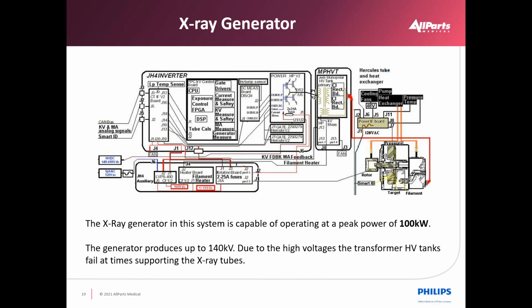So the area of challenges with regards to high voltage, when something degrades, it could be either in the tube or the high voltage tank. We would consider that a high voltage arc, and sometimes trying to determine whether it's a tube related arc or the high voltage tank itself causing the arcing, we have to kind of break the system down during troubleshooting. And also the connection of the high voltage cable into the high voltage tank. In this case, that connection can basically degrade, and we have to make sure that it doesn't have any air around that connection.